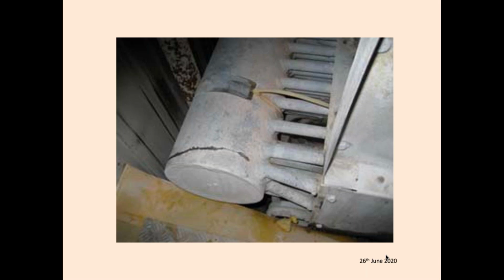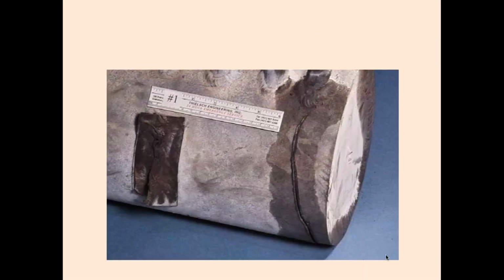A schedule 80 thickness A106 grade B pipe, and that is the wet return line. You can see how the end cap gets broken and the entire ammonia leaked because of this hydraulic hammer. So very important point. This is the photograph of the same. You can see how the end cap has totally collapsed, even if the correct pipe has been used. So it is very important how to design a plant with wet return and ammonia lines.